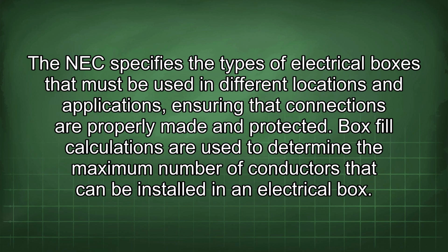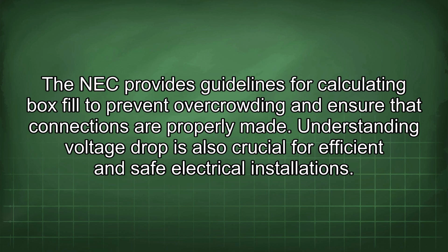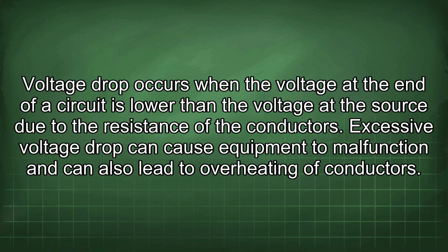Box fill calculations are used to determine the maximum number of conductors that can be installed in an electrical box. The NEC provides guidelines for calculating box fill to prevent overcrowding and ensure that connections are properly made. Understanding voltage drop is also crucial for efficient and safe electrical installations. Voltage drop occurs when the voltage at the end of a circuit is lower than the voltage at the source due to the resistance of the conductors.